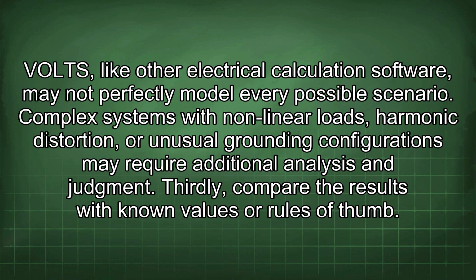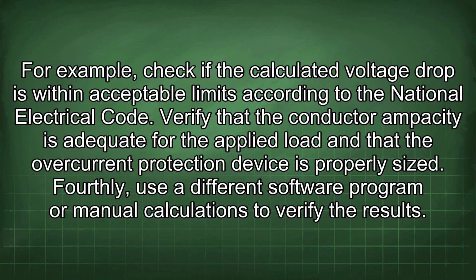Thirdly, compare the results with known values or rules of thumb. For example, check if the calculated voltage drop is within acceptable limits according to the National Electrical Code. Verify that the conductor ampacity is adequate for the applied load and that the overcurrent protection device is properly sized.